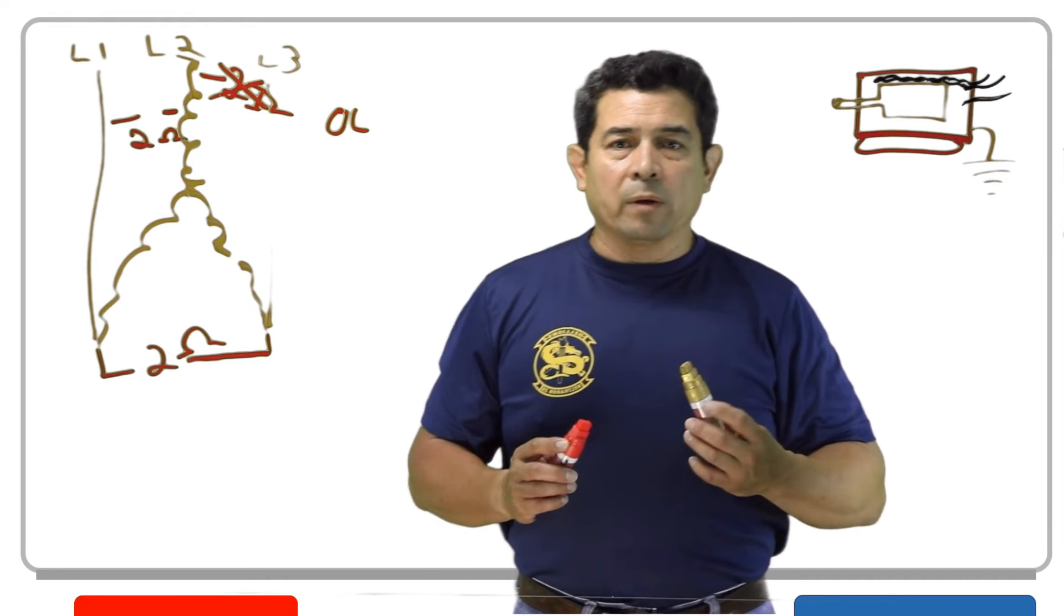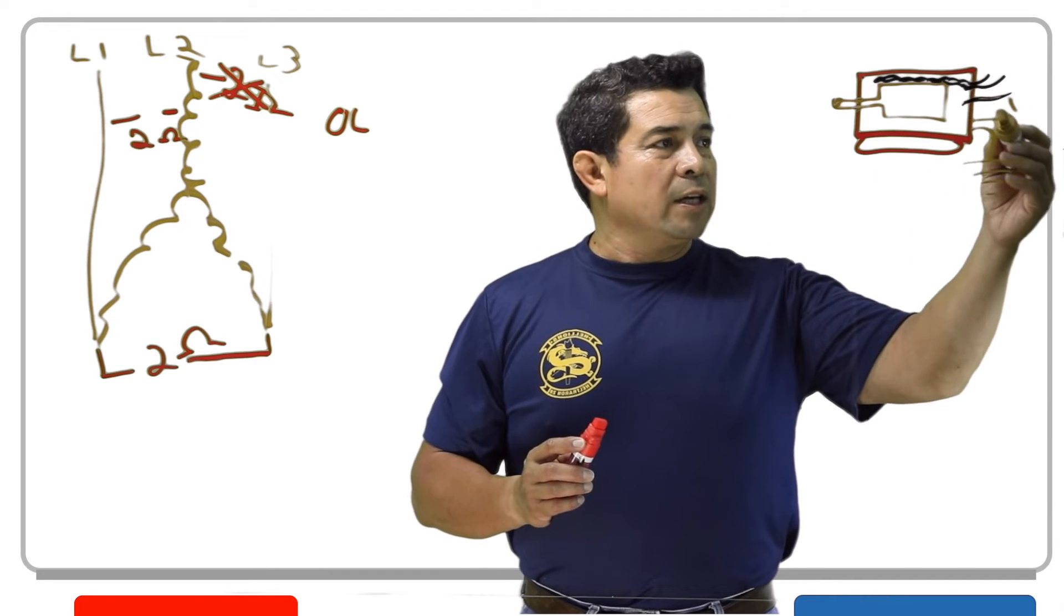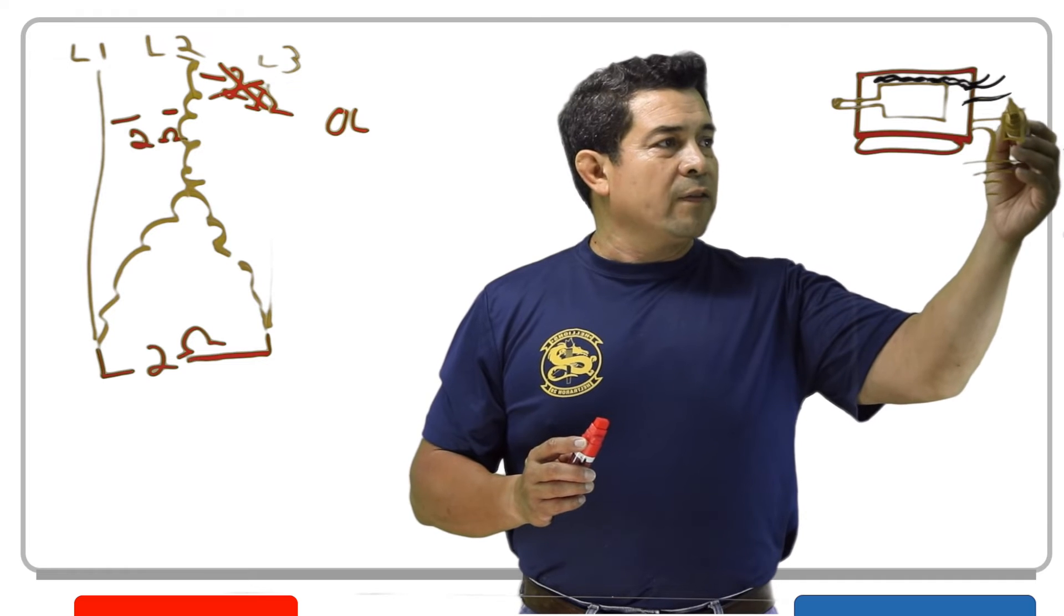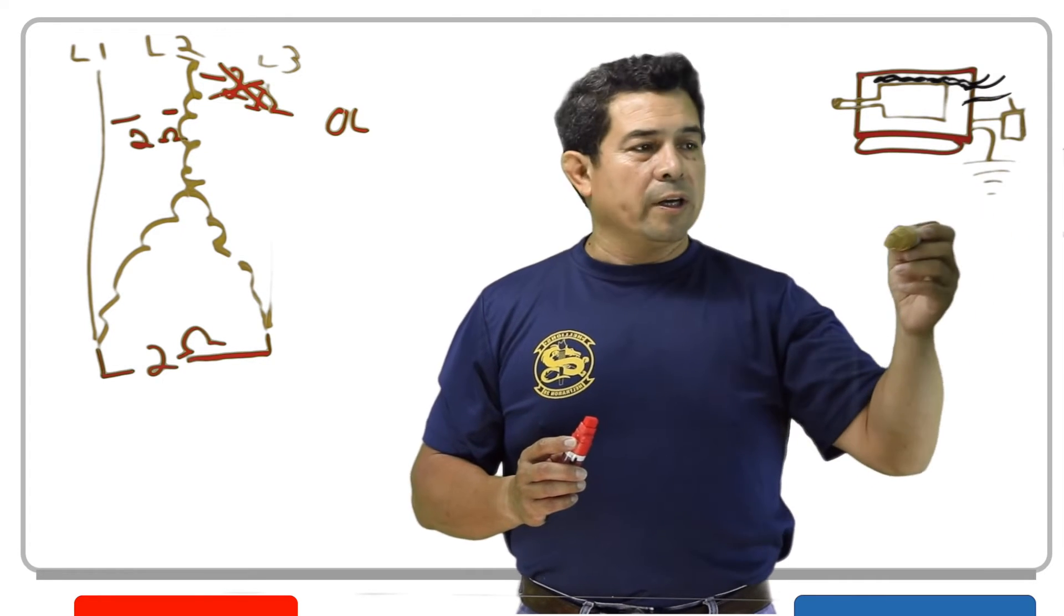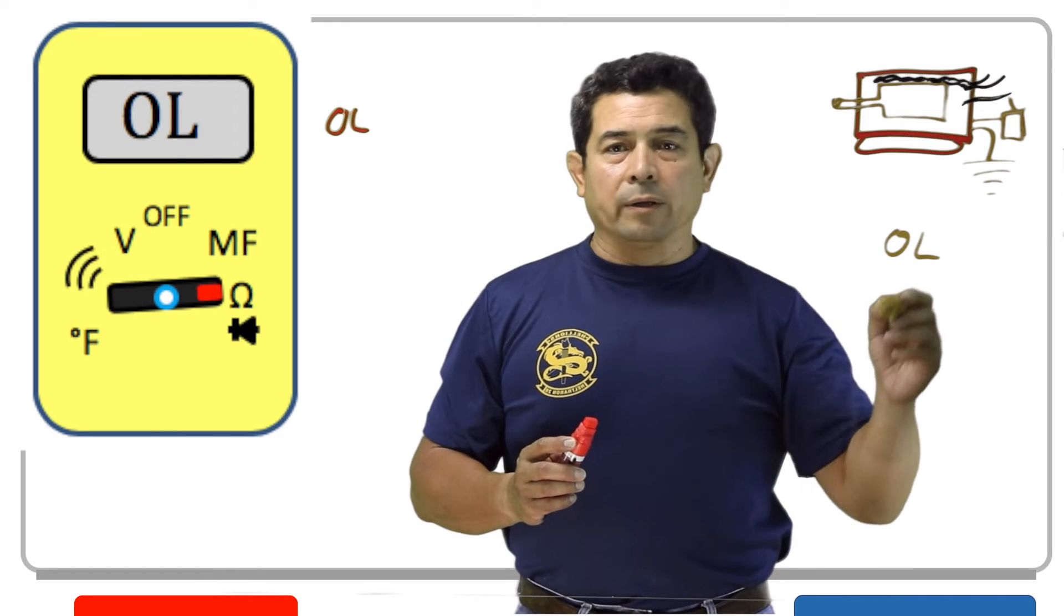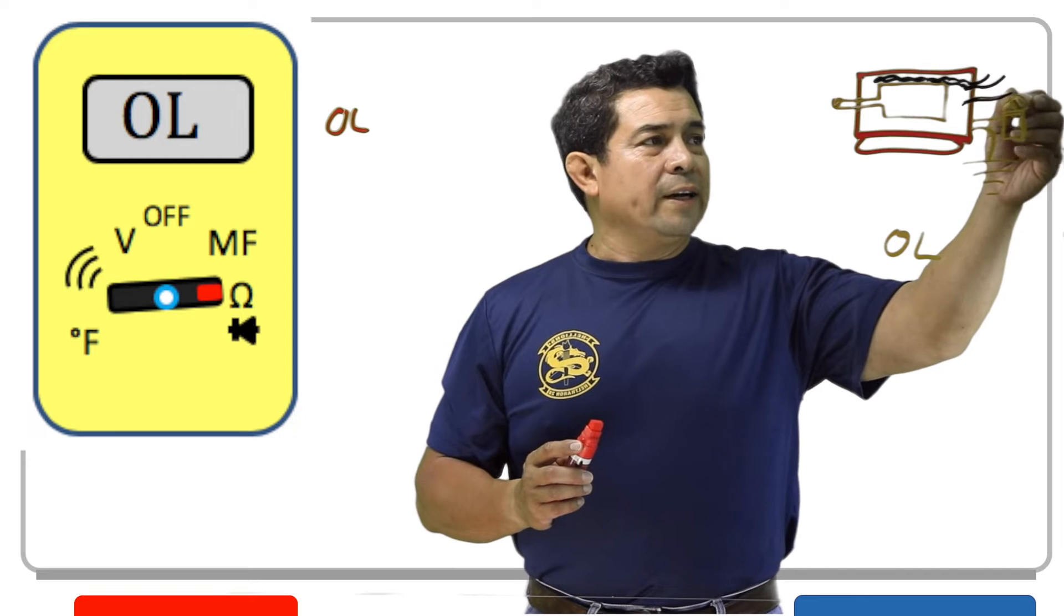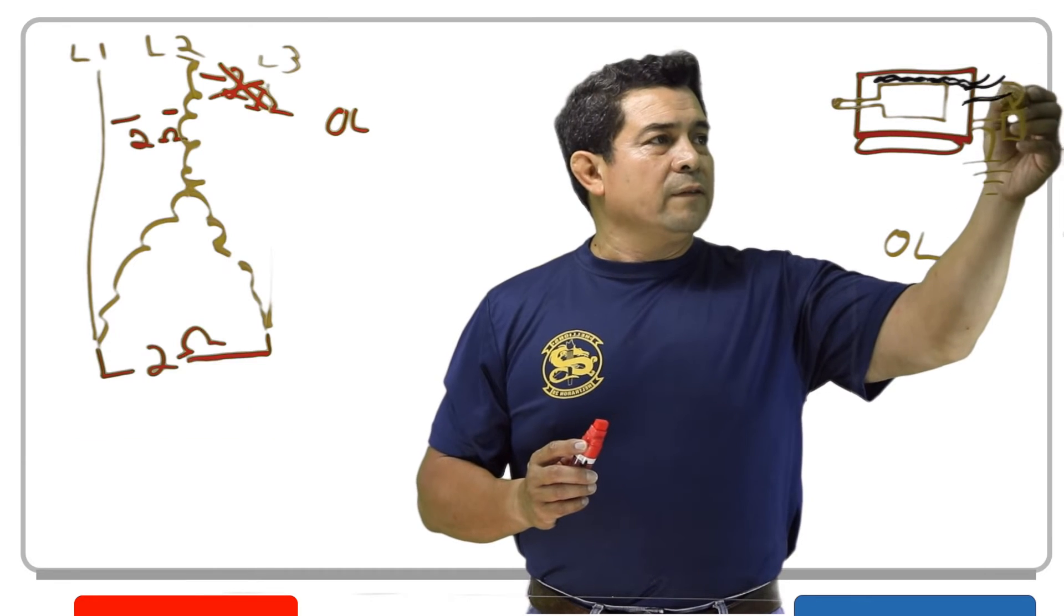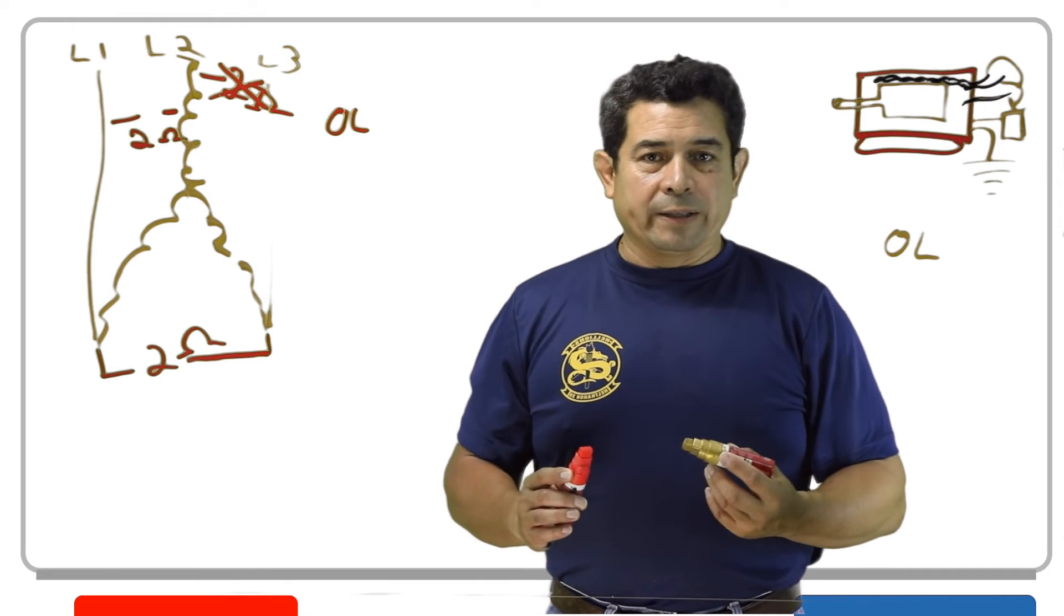Another check you might want to make is to go from one of the windings here to the casing. Once we check that on your meter, then we should get what? We should get OL, open lead or open line. We should never have a connection from any of these to the casing. If we do, then the motor is bad.